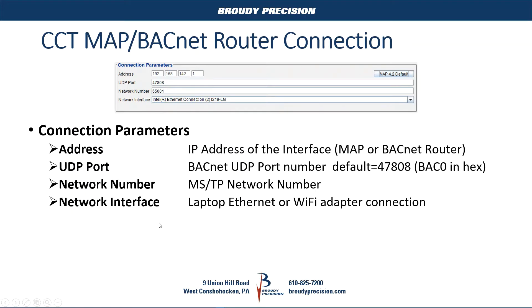The connection parameters have four fields: address, UDP port, network number, and network interface. The IP address is the address of the interface — whether it's the MAP gateway, a BACnet router, or the JACE. The UDP port is your BACnet port being used; the default standard port for BACnet is 47808, though you may need to change it based on your device's setup. The network number is your MSTP network number, not the BACnet IP network number. Your network interface is the connection from your laptop to that device, either a hard Ethernet connection or your Wi-Fi adapter.